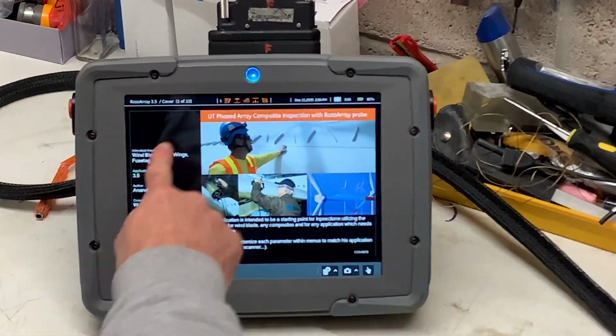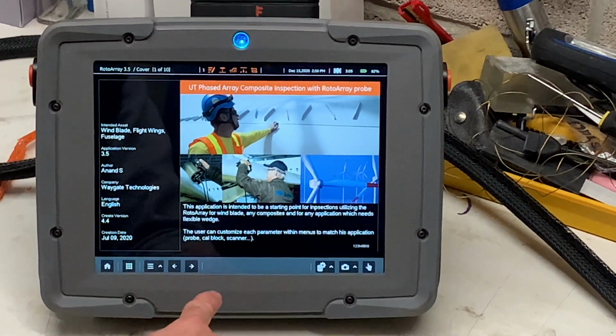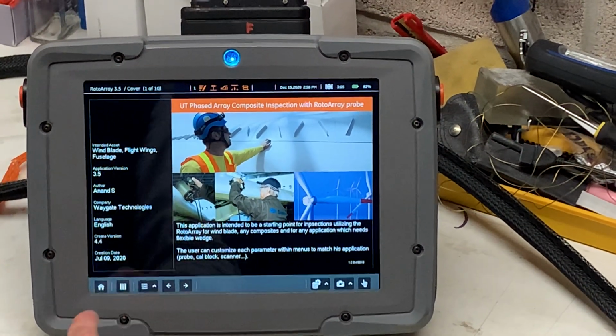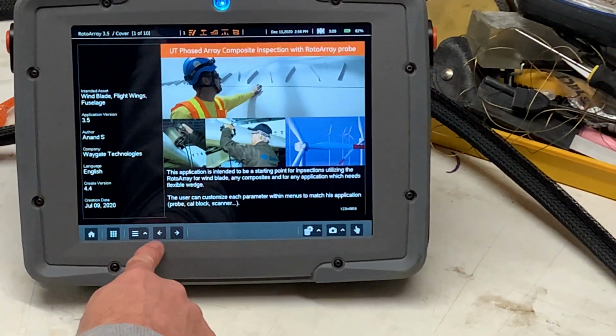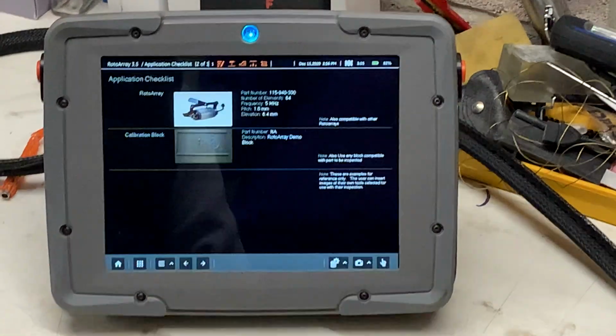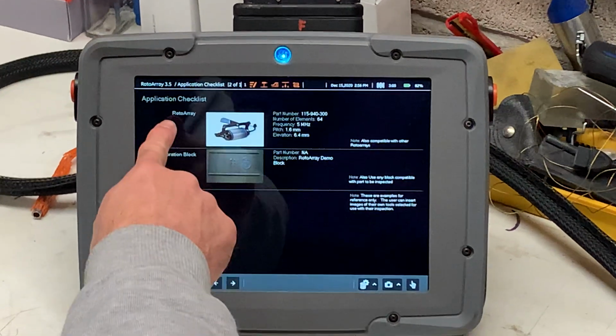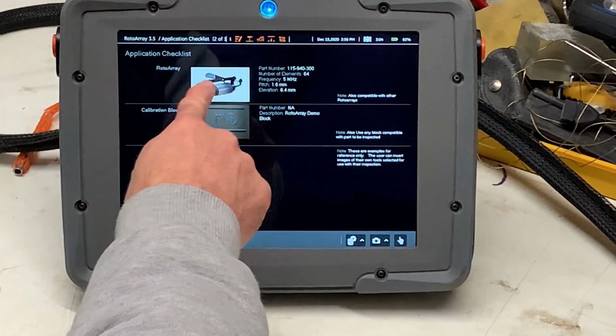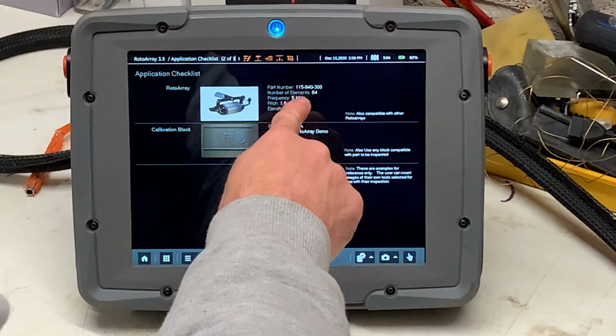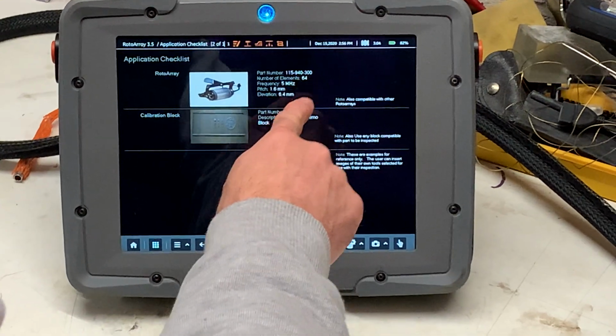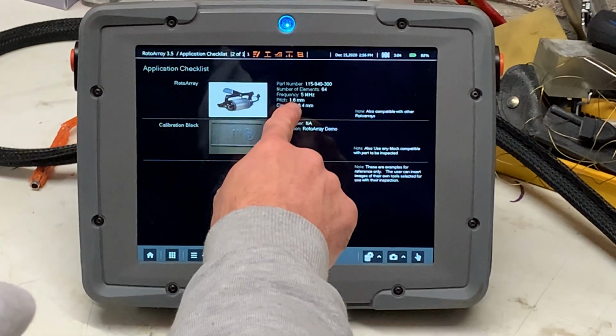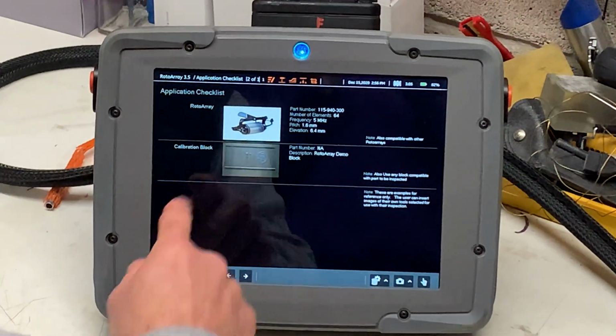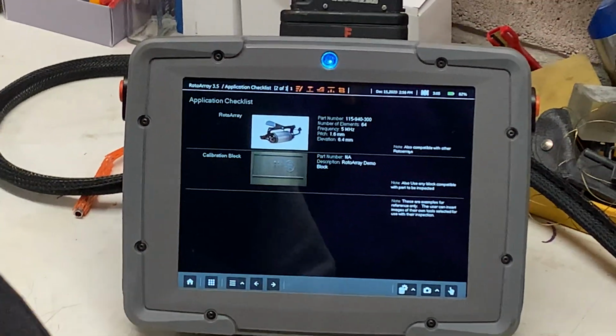So it's got 10 pages in it. The first page is this cover panel, which tells you what you're going to be doing and why you're going to be doing it. I'm going to use these arrow keys to navigate. So just press the arrow key, move to the next page. So the application checklist tells us we need this RotoArray. There's the part number, 64 elements, 5 megahertz, 1.6mm pitch. And then it tells us we need this calibration block, and it's got a picture of the old GE block, but we've got this new Waygate logo block.